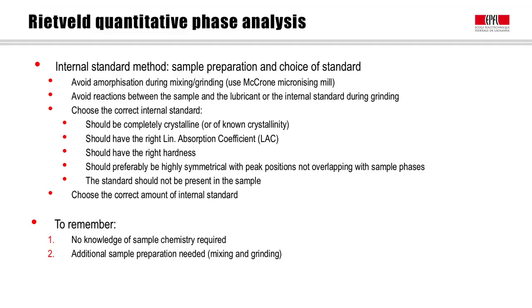Another property is that the internal standard should have known crystallinity — its amorphous content should be known and should not be present in the sample. Preferably, a standard material should have high crystal structure symmetry and have peaks that do not overlap with the main reflection peaks of the phases present in the material. In addition, it is good if there are no microabsorption problems, which would occur if there is a large X-ray absorption contrast between the phases in your sample and the standard. If this were the case, microabsorption problems may occur and one would have a falsified or biased quantification.